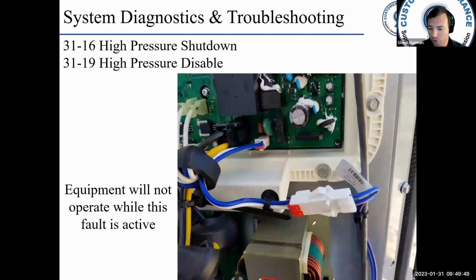Okay, here's another look at your high pressure switch. The wires come into this plug and you want to check this plug. Check the plug at the VFD. Make sure the wires are seated in the plug. Make sure it's making a decent connection there. If you are not making good connection, you could get a 3116.